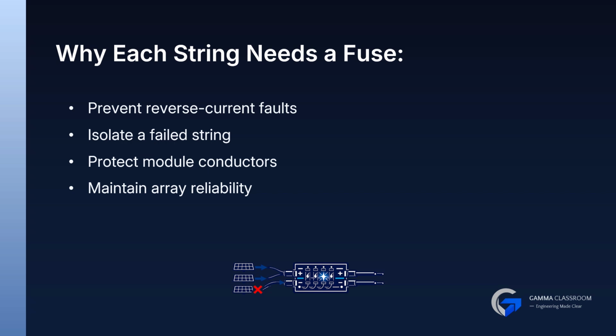When strings are in parallel, a fault in one string can cause reverse current from the others. String fuses stop that reverse current instantly, isolating the fault and protecting the modules. This keeps the rest of the array operating safely.